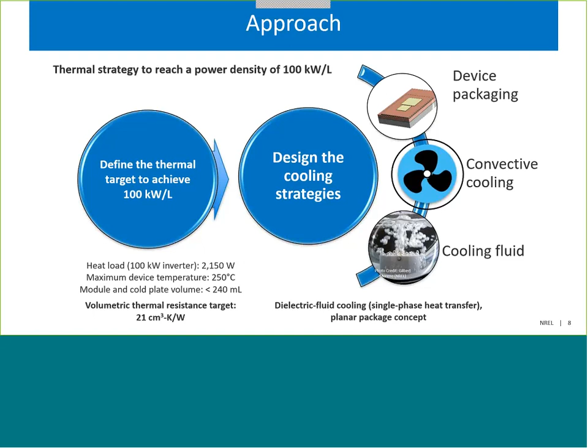This slide describes the dielectric cooling concept. Essentially, the concept uses a planar package where you have a MOSFET that's placed between two electrically conductive plates. The top plate is both an electrical conductor and also a heat spreader. We have a dielectric fluid that's impinging on the top surface of that external plate, so the fluid doesn't directly contact the device. The heat is being removed through single-phase heat transfer. We do need a dielectric fluid because the fluid is in direct contact with electrically active surfaces.